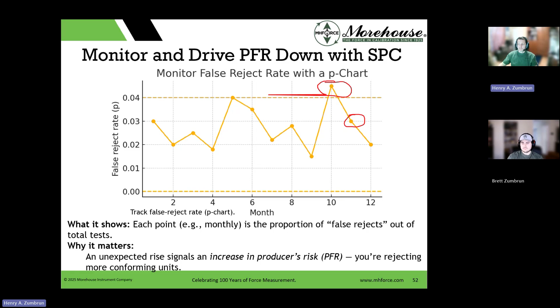The point is we are not infallible. Everybody makes mistakes. We have really low uncertainty, but paying all this attention to the charts and the historical data allows you to find this stuff really quickly. That's a situation where we had all that cal data, so we could go back and say, yeah, something's wrong here, and find it. And that's with low uncertainties. With high uncertainties, sometimes you can't see anything. You're just like, yeah, that's how it is, and then somebody has to live with it.